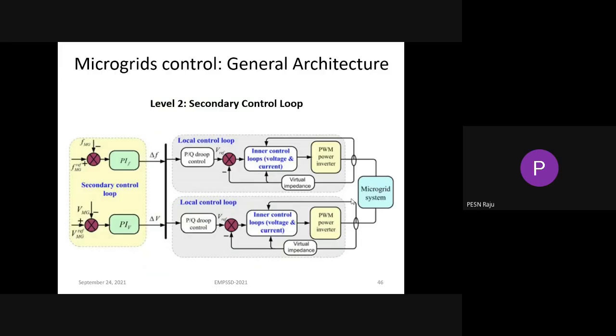And coming to the secondary level control loop, when there are frequency deviations or voltage deviations that the primary level control couldn't minimize, in that case, the secondary loop control will come into action, and it will minimize the frequency and the voltage deviations by taking the reference frequency value and the actual frequency value of the microgrid, and that will be passed through the PI controller. It will provide the deviation of the frequency, which we should add to the PF droop control or the QV droop control.